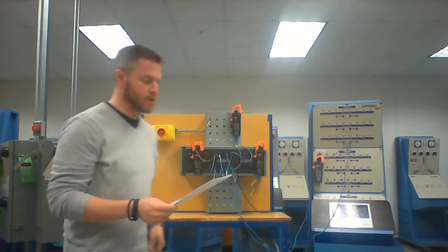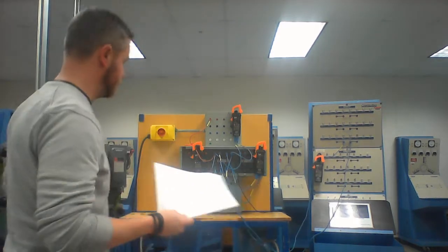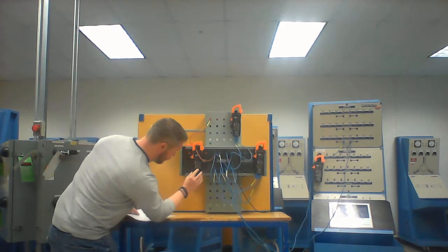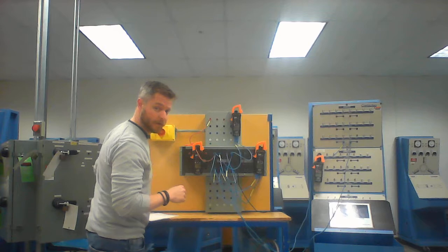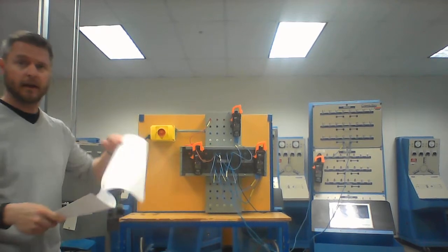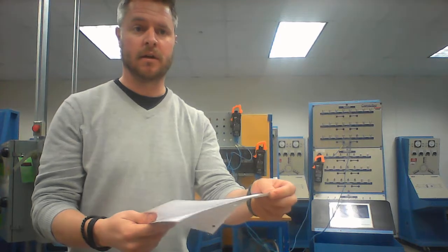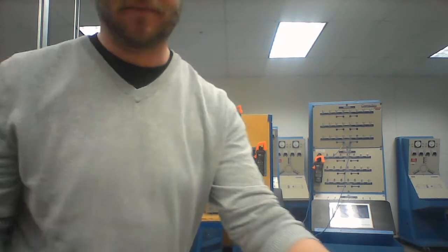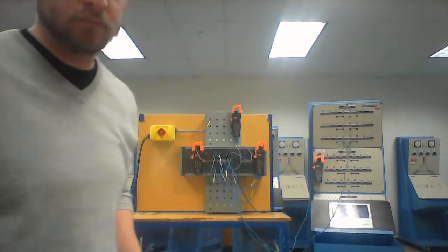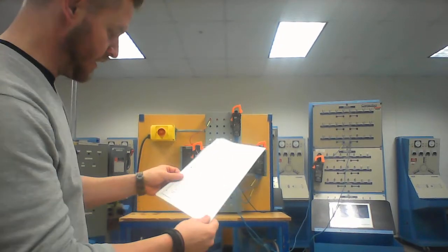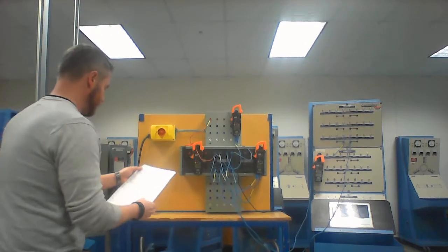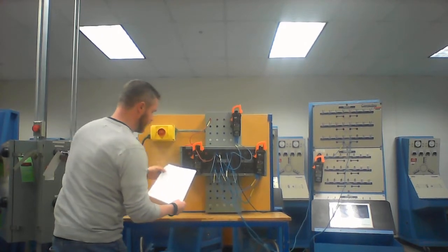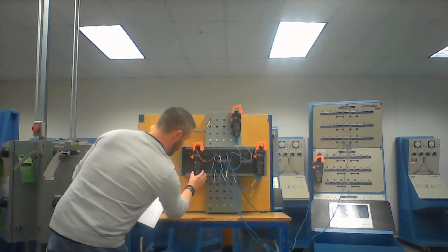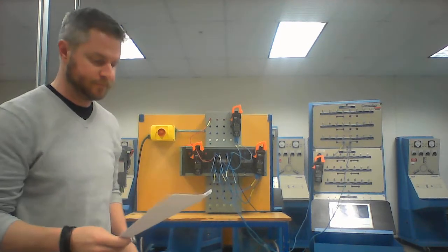So step number 10 says measure the primary current and compare it to the calculated value. Okay, so I've got my measurement here, and I see 0.37 amps primary current flow. Mike's got his calculated value for step number 9. We can pause it. Okay, so we do the calculation, and we are reading 0.427, the calculated value for step number 9, right there in the red box. And my red value, step number 10, measure the primary current and compare it to the calculated value. Measured value, 0.37 amps current flow, measured for step number 10. I'm pretty close.